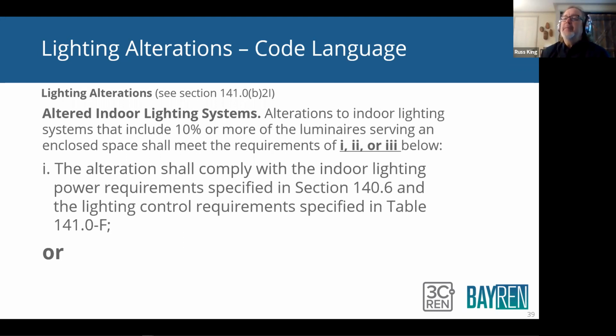Next, let's see, altered indoor lighting systems. This is the actual code language here. So those first three steps that I talked about, hitting your lighting power density and having some controls, beating it by 20%, or the relamping, replacing all the fixtures, we're going to look right now. I'm just going to show the actual code language for those three options. They're all right here in 141.0(b)2i, or I can't remember. Altered indoor lighting systems, alterations to indoor lighting systems that include 10% or more of the luminaires, we mentioned that, serving an enclosed space shall meet the requirements of 1, 2, or 3.